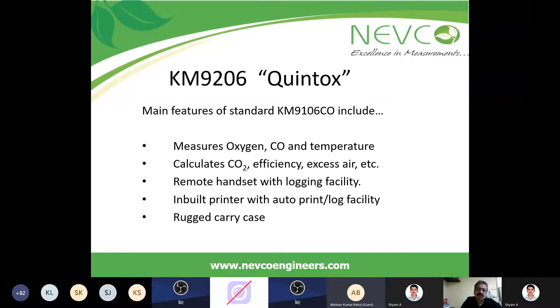So this is a flue gas analyzer, which is very versatile and has a built-in printing system here. You can see in the picture there is a small filtration system here and another 2 filters on the top, and then it measures most of the gases. The 9206 features include oxygen, CO measurement and temperature measurement, calculated CO2, efficiency, excess air, then a remote handset with logging facility, a built-in printer with auto print and log facility, then log cycle, and it can be upgraded for an emission monitoring system. 9206 options: we have NO, NO2, SO2 electrochemical sensors, CO high range electrochemical sensors, and CO2 is also directly measured with an infrared sensor.